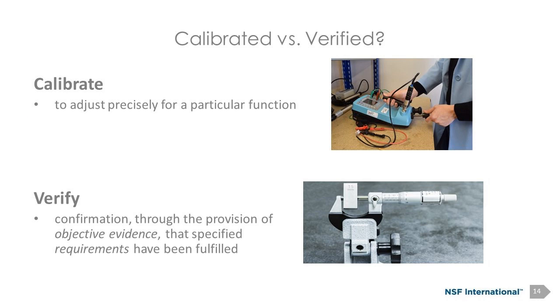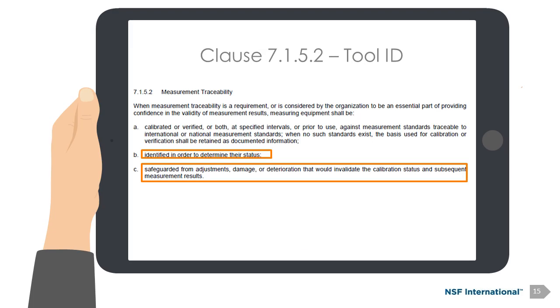With those definitions in mind, again, the standard requirement is we're going to calibrate or verify or both, because sometimes we do need to do both. We need to adjust offsets. We need to find a plane. We need to do that confirmation against a requirement, and then we make some adjustments for the environmental conditions that it's in, temperature, humidity, etc. Okay, in addition to that, we're going to do it at specified intervals. It doesn't prescribe timelines, and it also provides us the option of doing it prior to use against measurement standards traceable to international or national standards.